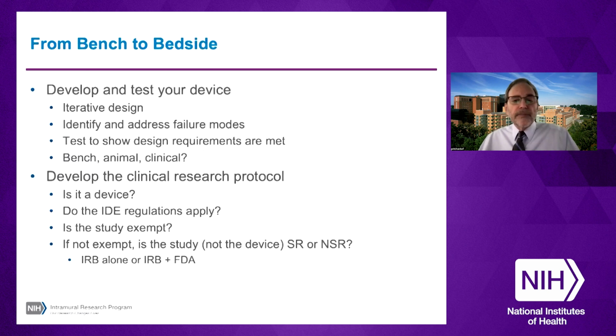So just in closing, when you're developing and testing your device, it's going to be an iterative design. You need to identify and address the failure modes, and then do testing that shows the design requirements are met, and that can include bench, animal, and clinical studies. For clinical studies, we talked about how to develop a clinical research protocol, and the questions in order: is it a device?